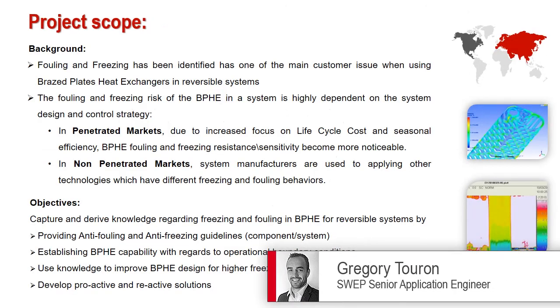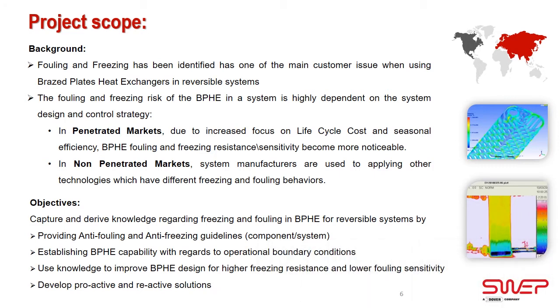If we take one step back and look at the heat pump market globally, we can divide it into two kinds of markets. The first one is what we consider a mature market, like in Europe or to some extent in Asia. In these markets, BPHE is the standard heat exchanger technology, but due to market change, system manufacturers have to extend the envelope of their product without any compromise in terms of system reliability. Due to this new market requirement, BPHE freezing and fouling behavior is getting more and more noticeable.